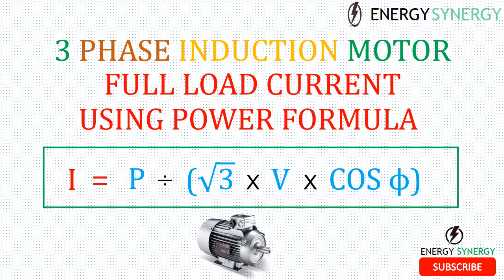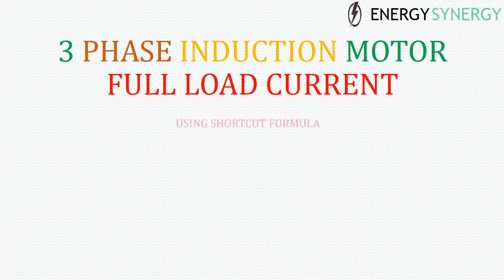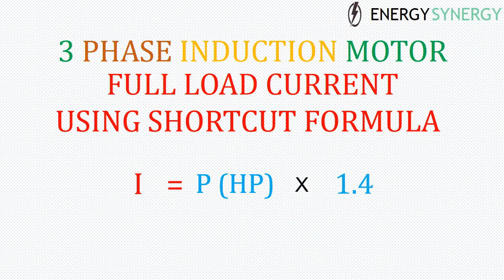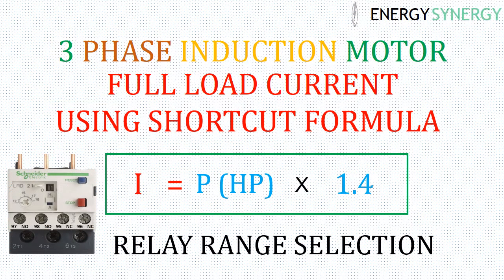Since there are a large number of motors in industries, it is not always practical to use that formula. So there is a shortcut method: the shortcut formula for calculating full load current of a three-phase induction motor is Full Load Current = HP × 1.4, where 1.4 is a multiplication factor. This formula is generally used to calculate the relay range for a motor. Please note that when you calculate current using this formula, you may get a small error in values, generally in decimal points.